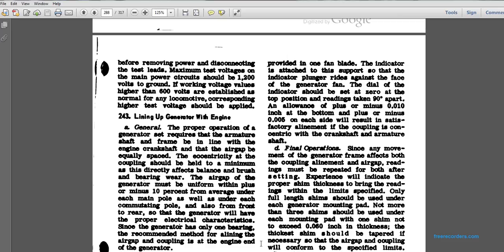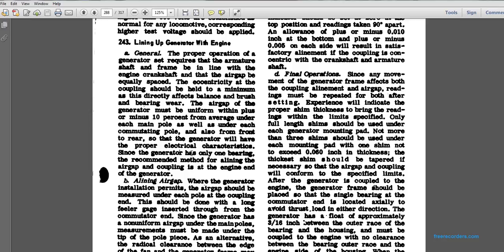The indicator is attached to the support so that the indicator plunger rides against the face of the generator fan. The dial of the indicator shall be set at 0 at the top position. Readings are taken 90 degrees apart. An allowance of plus or minus 1/100 of an inch, or 5/1000ths of an inch on each side, will result in satisfactory alignment of the coupling, engine crankshaft and armature shaft. Final operation: since any movement of the generator frame affects the coupling alignment and the air gap, readings must be repeated after both settings.